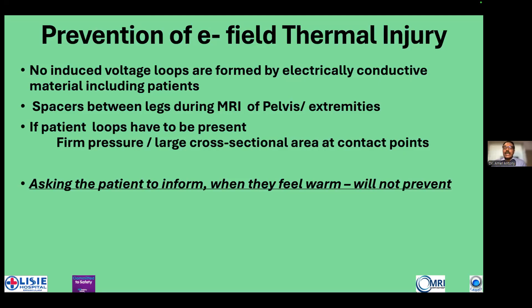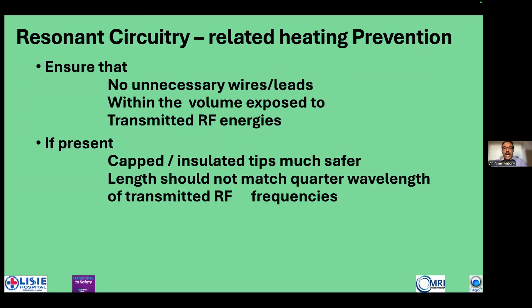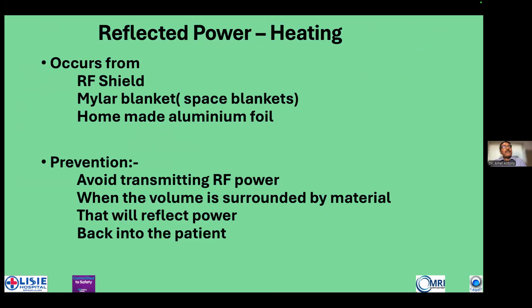And when we have loops of connectors or catheters, this again can be a cause for heating. So whenever we have such circuitry, we should ensure that unnecessary wires and leads are not placed. And wherever the patient is exposed to radio frequency, we should see to it that the wires are straightened out, and capped and insulated wires are much safer. And finally, reflected power heating can also occur from the RF shields and various blankets which are used, or homemade aluminum foils which are used. So we have to ensure that such things are not there in the radio frequency coil field.